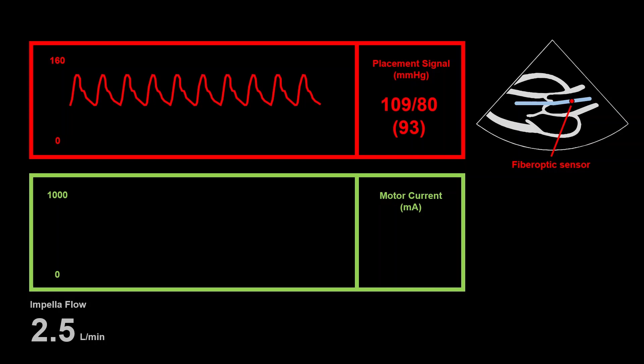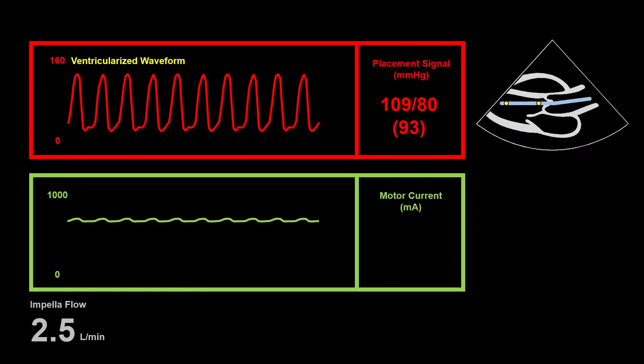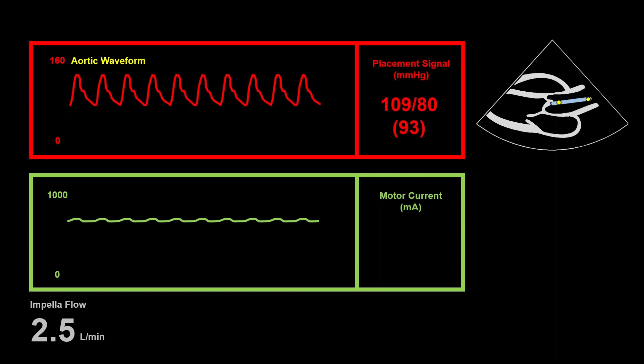When the Impella is properly placed, the motor current will be pulsatile, with peaks when the aortic valve is open and there is more energy and flow, and valleys when the aortic valve is closed and there is less energy and flow. When the Impella drifts out of position, the motor current will be flat because the aortic valve is no longer creating a pressure gradient across the cannula. A flat motor current, coupled with a ventricularized waveform pattern, indicates the Impella has slipped too deep into the ventricle, whereas a flat motor current coupled with an aortic waveform pattern indicates the Impella has slipped too far into the aorta.